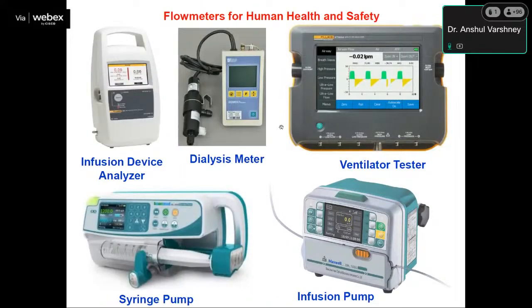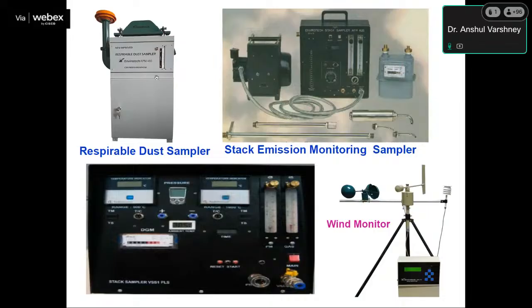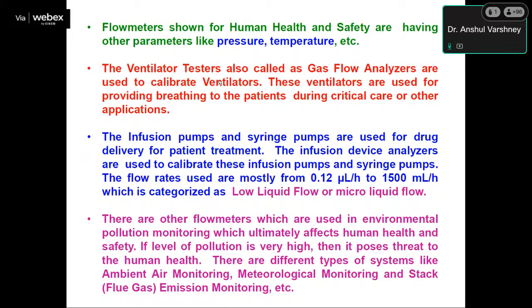These are some flow meters which are used for human health and safety, like infusion device analyzers. These types of flow meters are used in hospitals, and include dialysis meters, ventilator testers, syringe pumps, and infusion pumps. So these are some other types of flow meters which are used for human health. These are from the environmental area, like respirable dust samplers, stack emission monitoring systems, and wind monitors. The flow meters shown for human health and safety also have other parameters like pressure, temperature, etc.